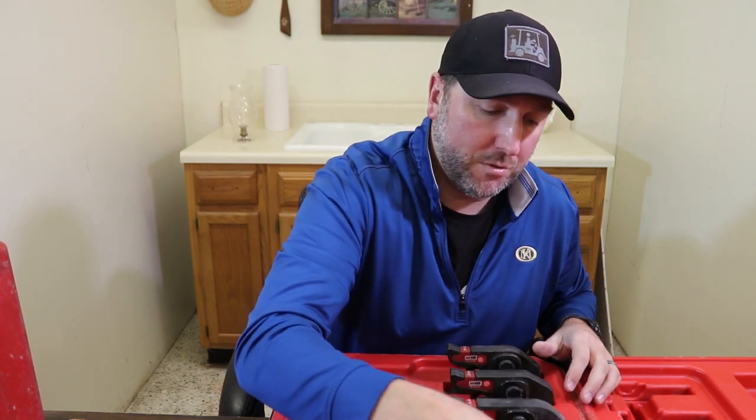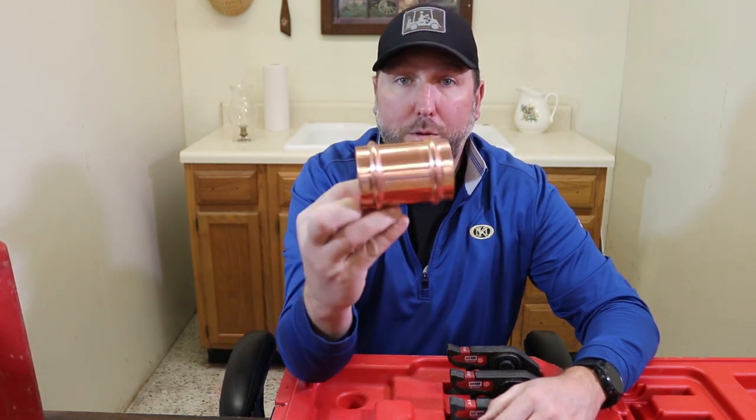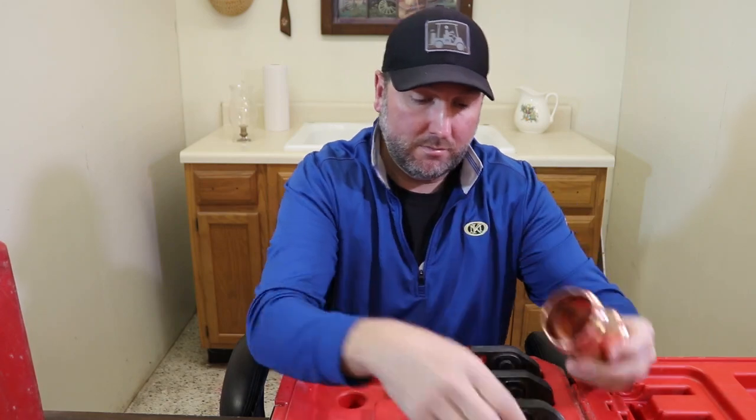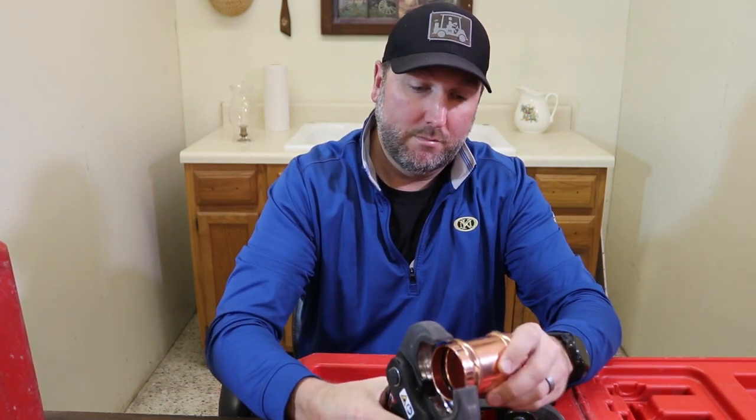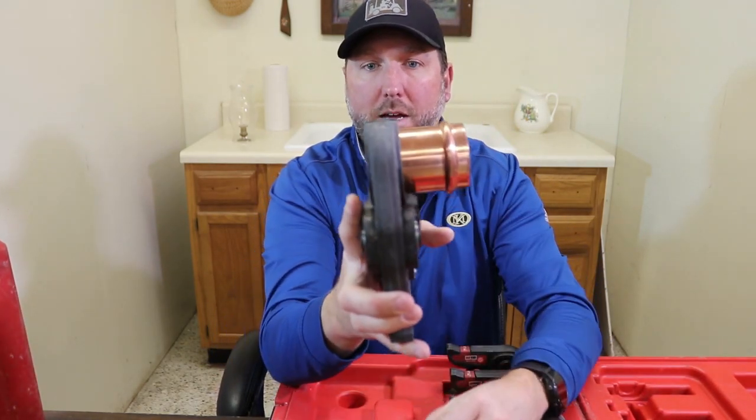There's the size of the two inch jaw. It really comes in handy when you have a situation where an apartment complex or hotel has a leak and you've got all these floors above you. When you cut the water off, it has to drain down, and that could take a couple hours depending on how many floors you have. Some situations you can't solder because of water in the system — you can make a repair, put a coupling in, slide it over, and crimp it, and be in and out in no time.